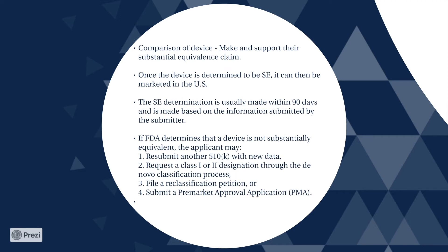If FDA determines that the device is not substantially equivalent, the applicant may resubmit another 510(k) with new data, request a Class 1 or Class 2 designation through the De Novo application process, file a reclassification petition, or submit a pre-market approval application.